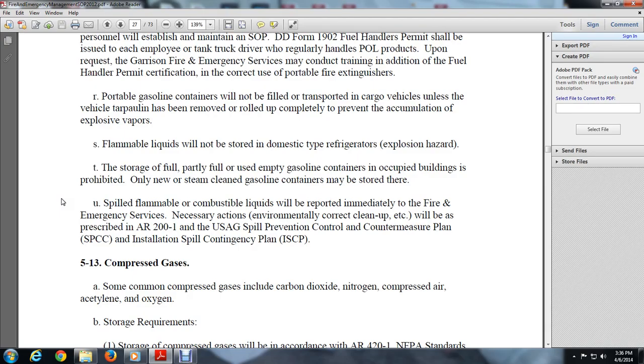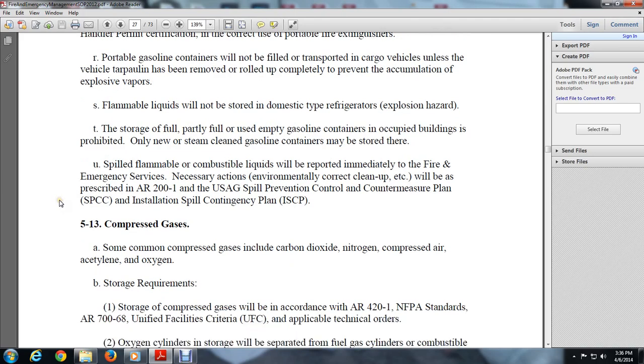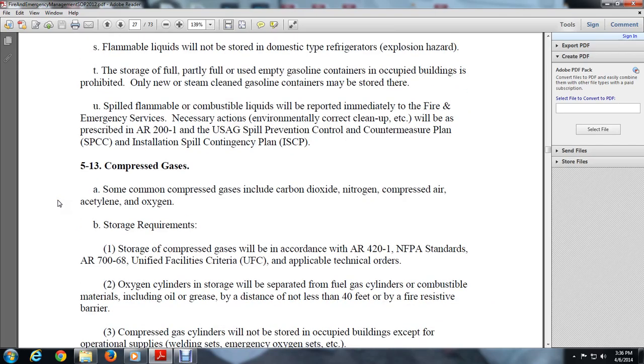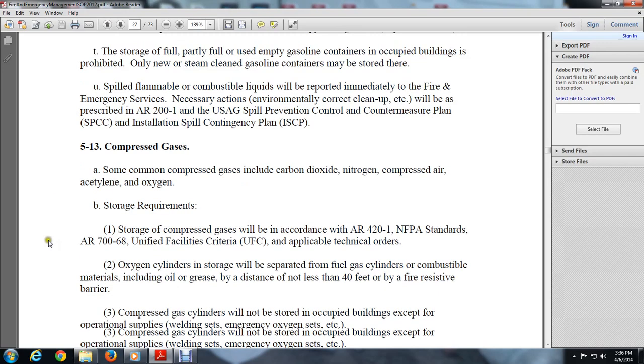Compressed gases. Some common compressed gases include carbon dioxide, nitrogen, compressed air, acetylene, and oxygen. B, storage requirements. One, storage of compressed gases will be in accordance with AR 420-1, NFPA standards, and AR 700-68, Unified Facilities Criteria, and applicable technical orders. Two, oxygen cylinders in storage will be separated from fuel gas cylinders and combustible materials, including oil and grease, by a distance of not less than 40 feet or by a fire-resistive barrier.